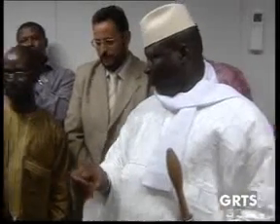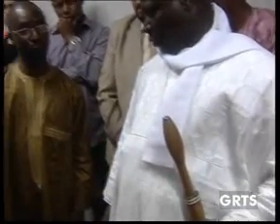But this is still moving up. It says maximum available kilowatts. It's still going on, and the engine is not on. Why? Because that's the setting. You can have an installed capacity and then the available capacity, because it also depends on the temperature and other operating conditions. So normally you don't give it 100%, maybe you give it 85%, 90%, and that is what it is showing there. It is showing 0 because it's not starting. Okay, so can we start now?